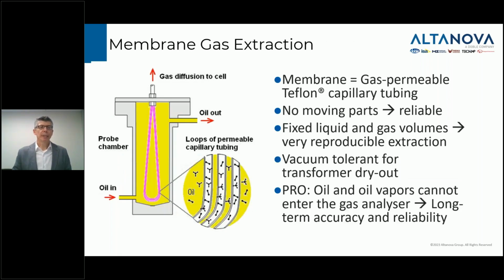So the other way of doing the gas extraction, which is the approach that our products prefer, is what we call a membrane gas extraction. Here, the membrane is most commonly in the form of gas permeable Teflon tubing, thin-walled Teflon tubing that's immersed in the oil. As shown in this image here, in this particular case, there are multiple loops of this tubing that are bent back so that they all exit the oil container at the same point. But there are other configurations as well.